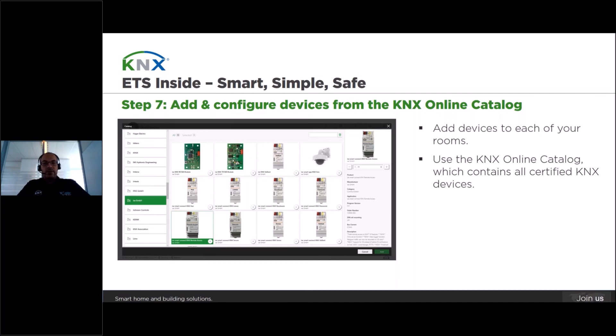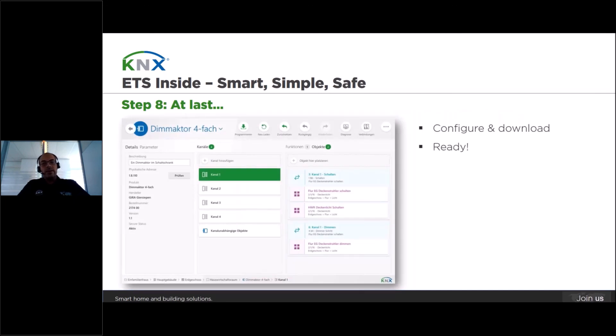Once the building structure is set, you have to add the devices in the corresponding location by using the online catalog, which contains all the KNX certified devices that are in the market and are compatible with ETS Inside. Since all devices have now been properly allocated, you can start linking the building functions with the respective device channels. Once the configuration is ready, download it to the devices and you're ready to go. ETS Inside has all what is needed to set up a KNX installation with only a few taps on the screen.